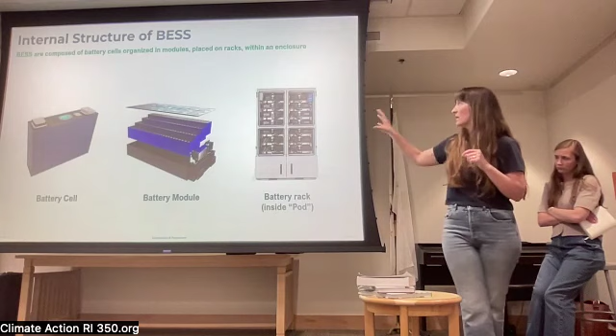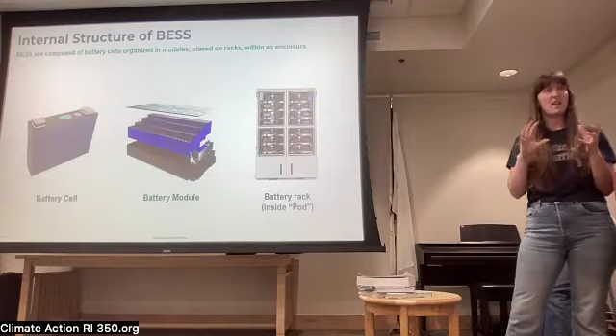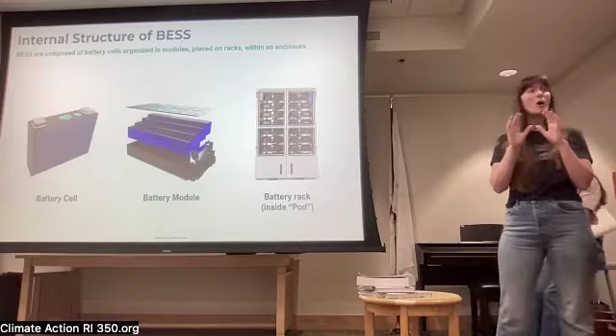It starts at the cell level. On my right, you can see the battery cell, much bigger than they actually are. Many battery cells are organized into a module, and then the modules are organized onto racks. As you can see, there are 2 racks there. This is a pod, a certain amount of racks enclosed in a system. With the Megapack, they don't use pods. This Fluence product, another manufacturer, does use pods. So there's different terminology with each product, but generally they're all cells organized into modules, housed in racks, all within the enclosure.